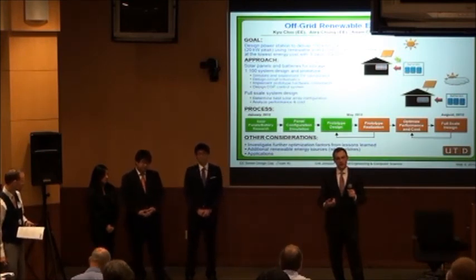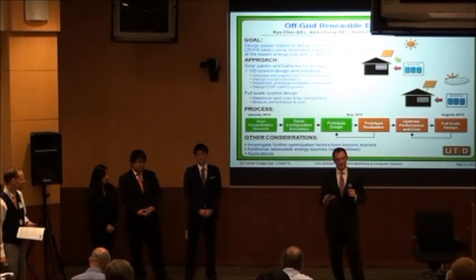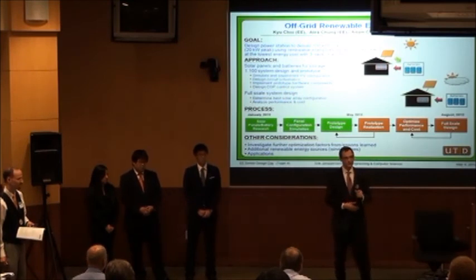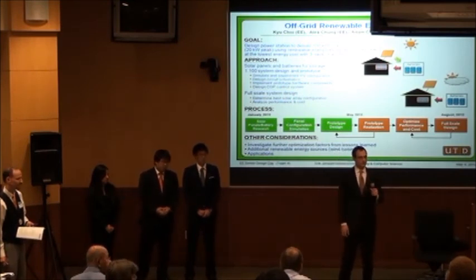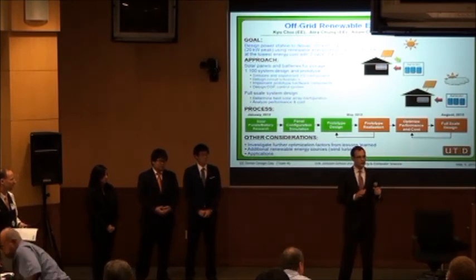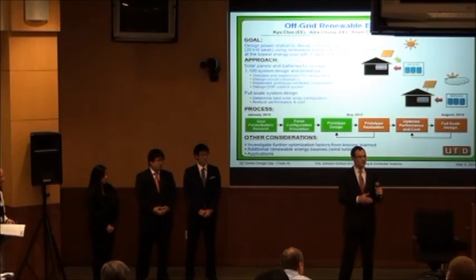So if we're wanting to have 100 kilowatt hours of energy per day, we would actually need 400 kilowatt hours of energy storage. But in addition to that, we have to maintain the batteries above 60%. So there's going to be a lot of batteries for sure. That's based on the deep cycle marine batteries, you can't go below 60%. This is based mostly on the statistic.